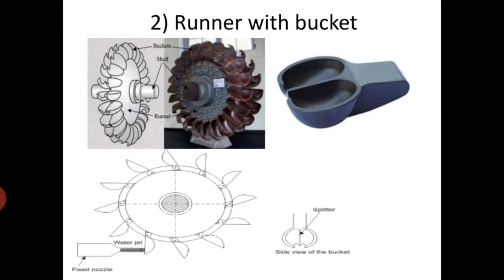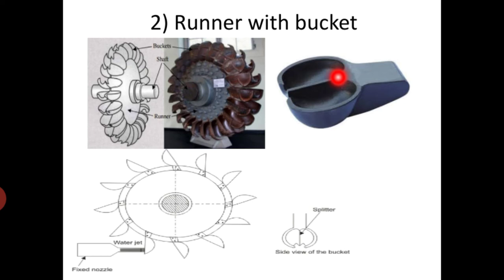The shape of the bucket is like two spoons joined together. The bucket has a common dividing edge. The incoming jet of water meets the bucket at the central edge, which is called the splitter. The jet strikes at the center of the bucket at the splitter, which divides it into two parts, and after turning through 160 to 170 degrees, the water leaves from the outer edge.